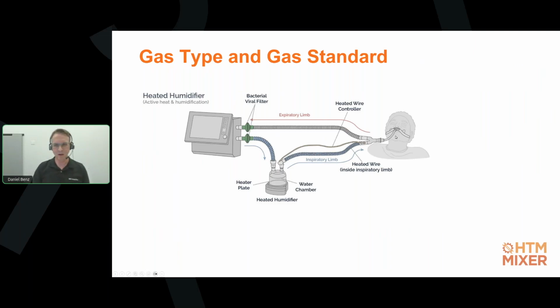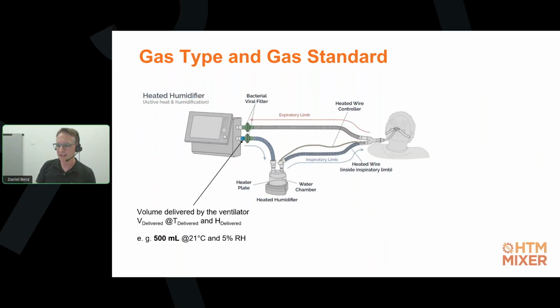Here it's just a mask, but it could also be a tubus. And then we have a second limb for the exhaled gas that actually goes back to the ventilator, to the exhalation port. So let's assume in this specific example that this ventilator delivers a volume of exactly 500 milliliters, measured at the output of the ventilator by its internal sensors. And let's assume that this ventilator takes air from a compressor system, so it is going to be pretty dry, and that it has a temperature of 21 degrees Celsius.